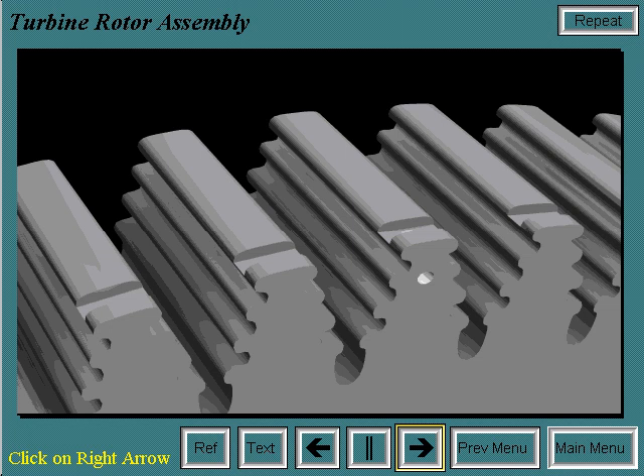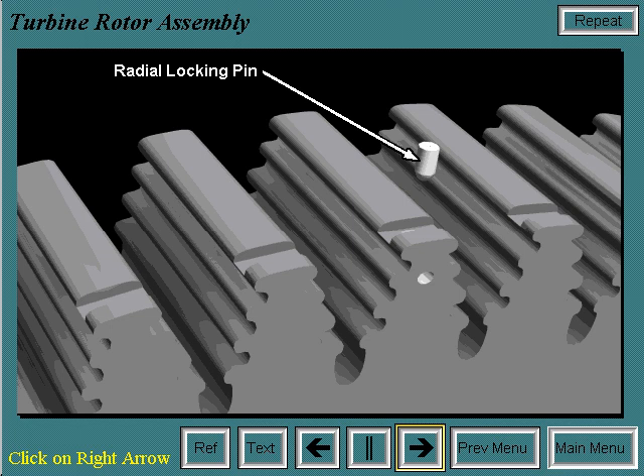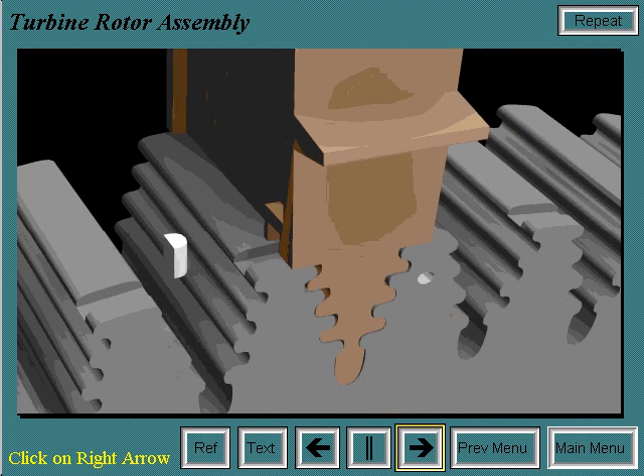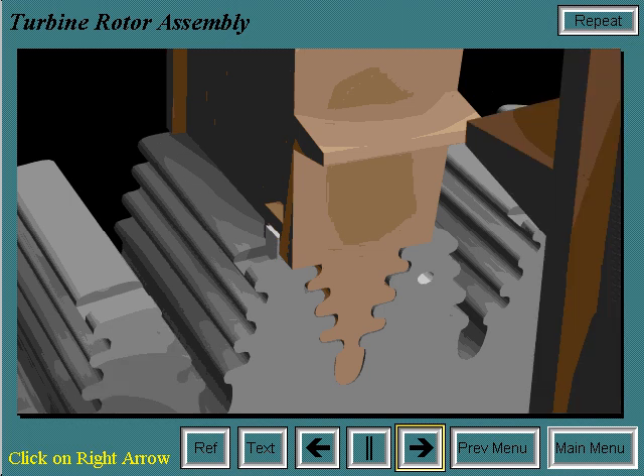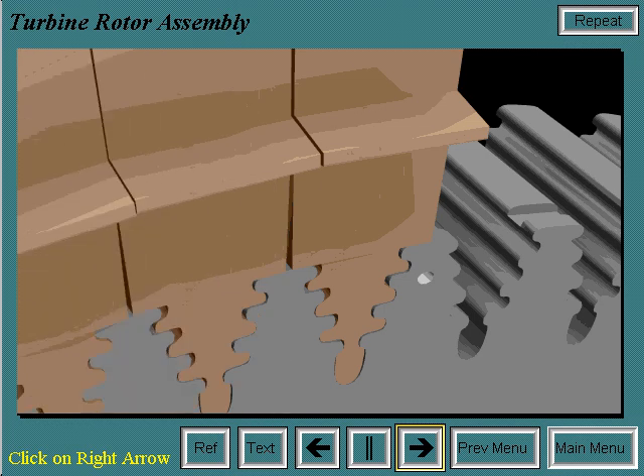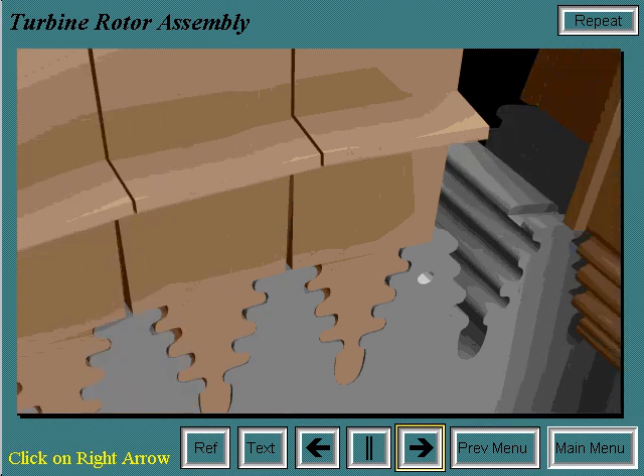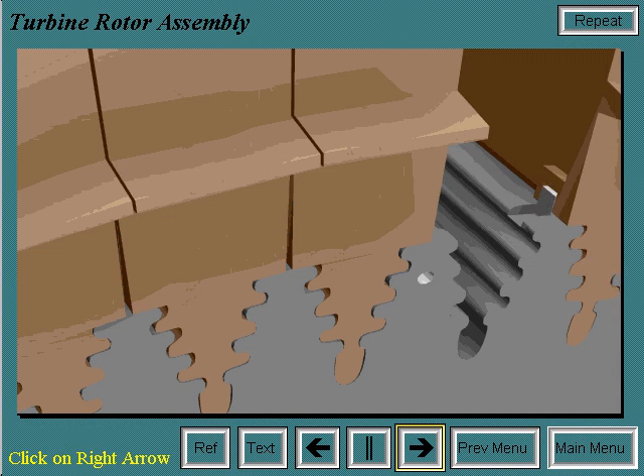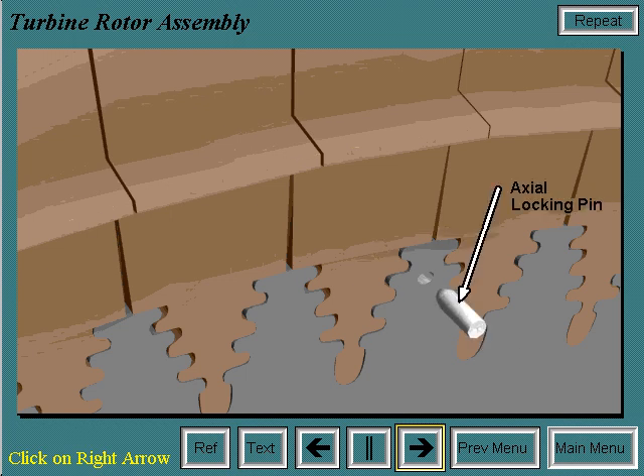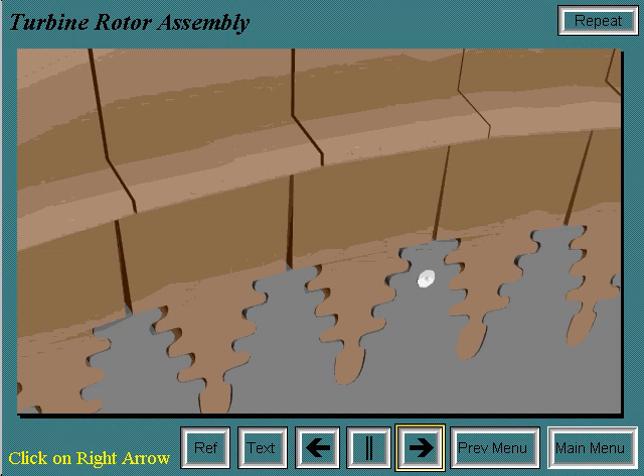The first step of installing the first stage buckets to the turbine wheel is to insert the radial locking pin into the locking bucket dovetail. The first bucket is installed in the counterclockwise adjoining dovetail slot and is held in place with a D key. The remainder of the buckets are installed in this fashion, working around the wheel counterclockwise. The last bucket is installed into its dovetail and the axial locking pin is driven into the wheel, pushing the radial locking pin up to hold the last bucket in place. All the buckets are now locked onto the turbine wheel.